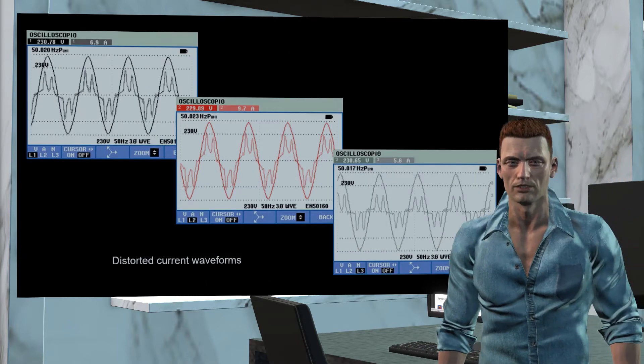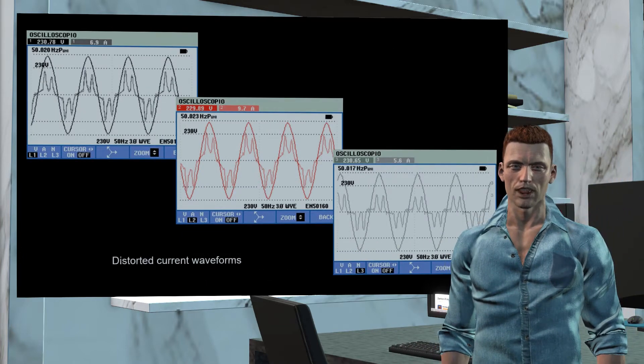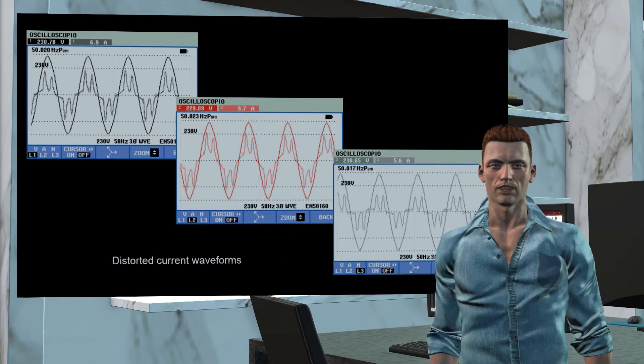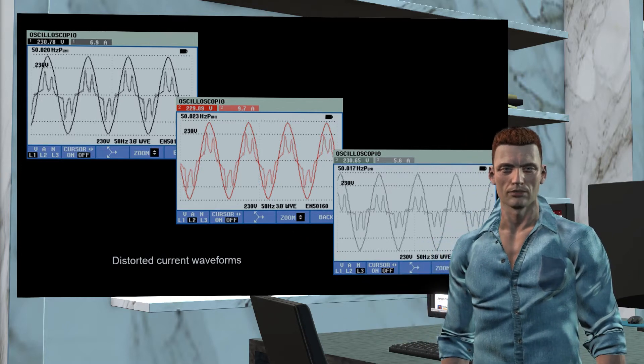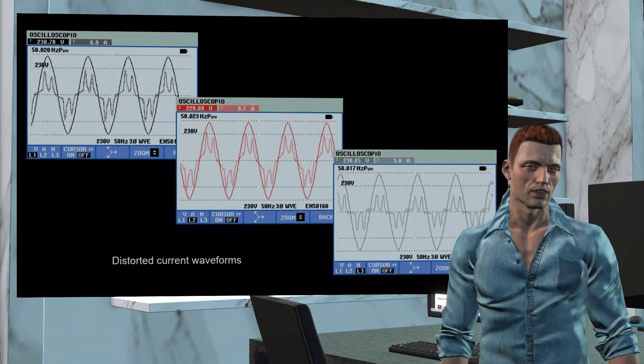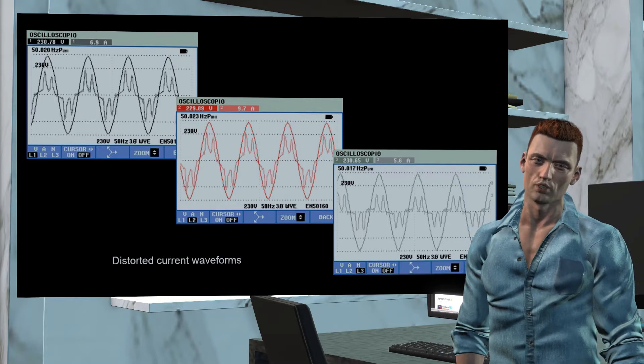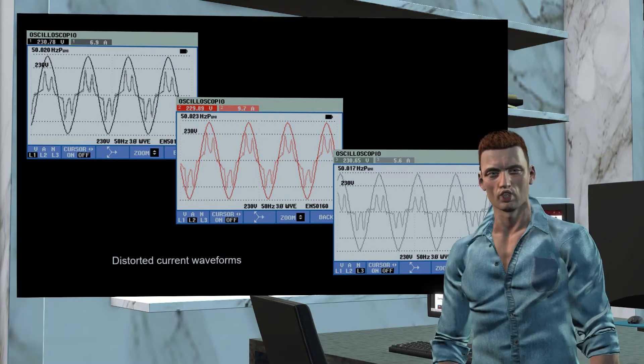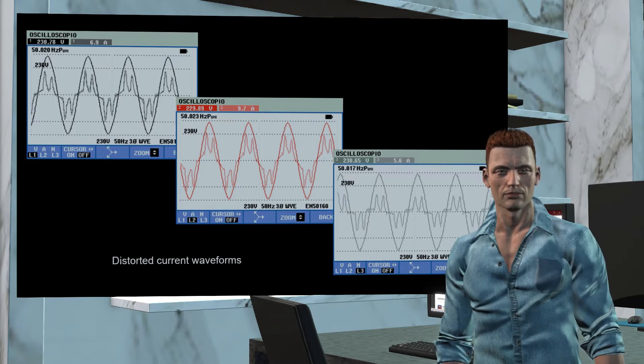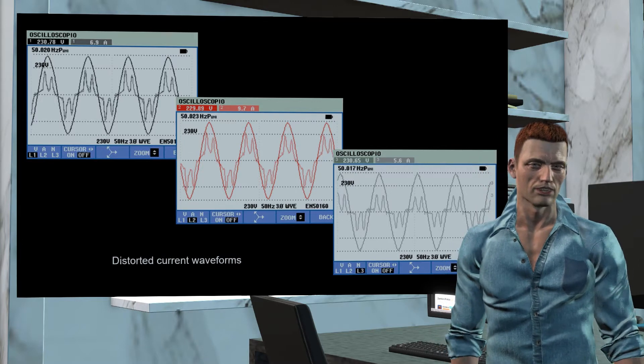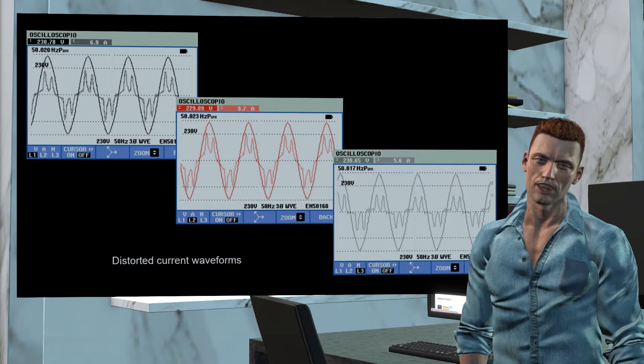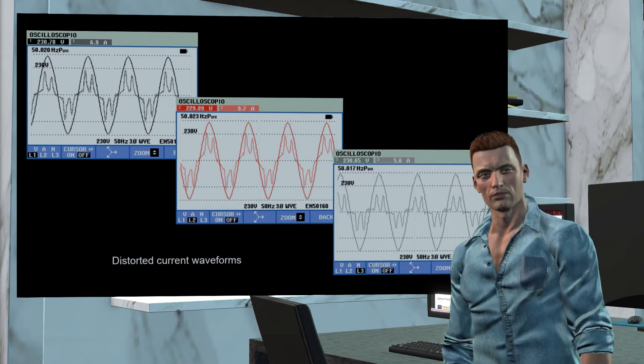The waveforms of the currents depend on the type of loads connected to the network. In general, linear loads will also give rise to currents with a sine wave shape. Non-linear loads will result in distorted currents. In this example we can see the voltages and currents associated with a three-phase rectifier. The voltages are more or less sinusoidal, however, the associated currents are highly distorted.